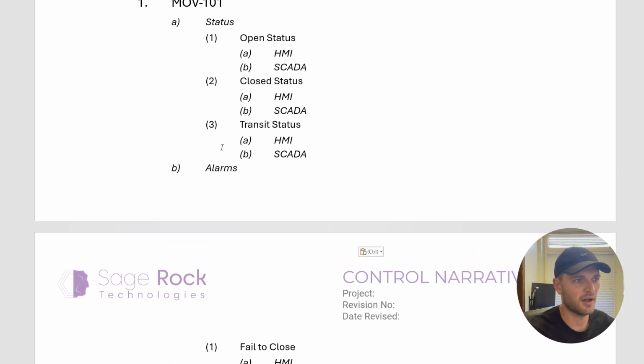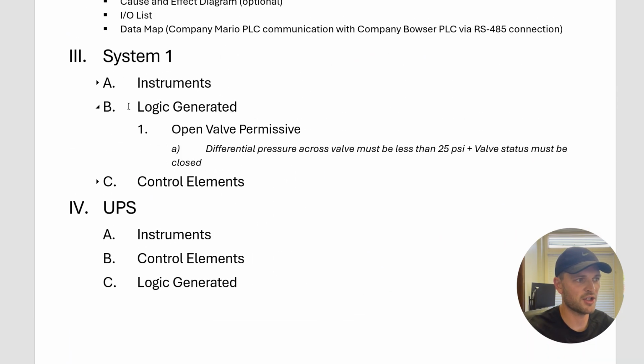One more thing to point out on the logic generated items. This is where I think control narratives beat cause and effect diagrams because, A, cause and effect diagrams can be really big. The little squares are really tiny, so it might be hard to see the inputs and outputs. And also, if you have a chain of inputs that generate an output that is used maybe to control a valve, it's hard to depict that when you have inputs on your rows and outputs on your columns, right? How do you notate that multiple devices actually close a certain valve? If you just write it down in words, there's no confusion. You don't need any notes, and you don't need a microscope to read the document.